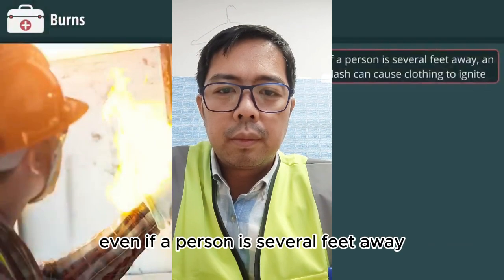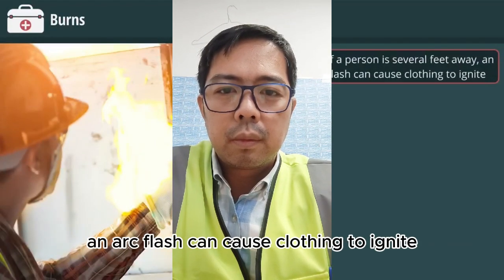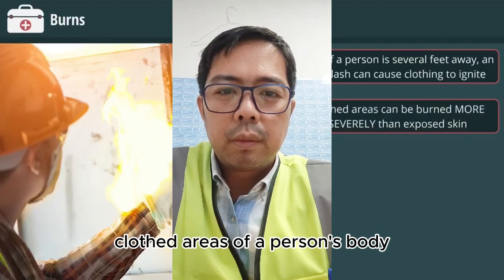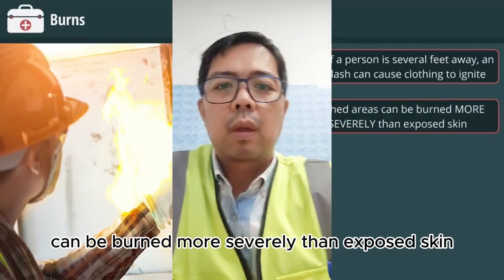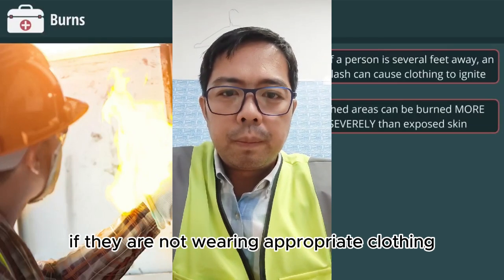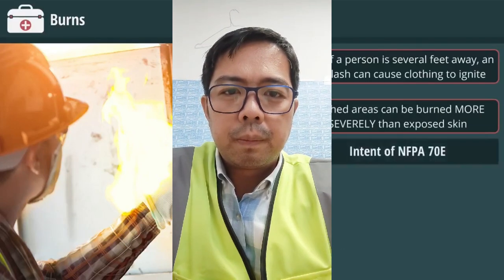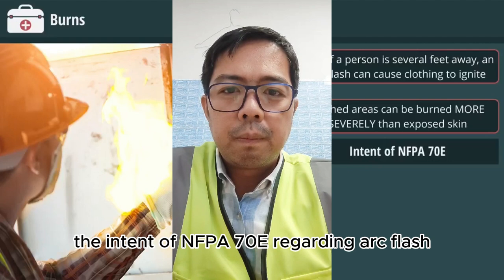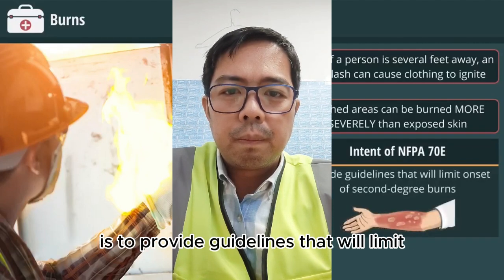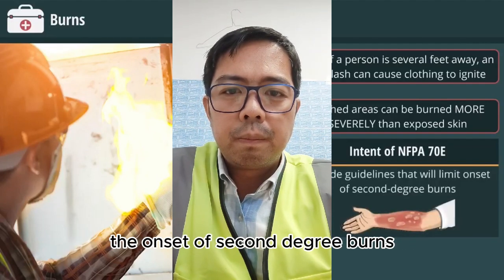Even if a person is several feet away, an arc flash can cause clothing to ignite. Clothed areas of a person's body can be burned more severely than exposed skin if they are not wearing appropriate clothing. The intent of NFPA 70E regarding arc flash is to provide guidelines that will limit the onset of second-degree burns.